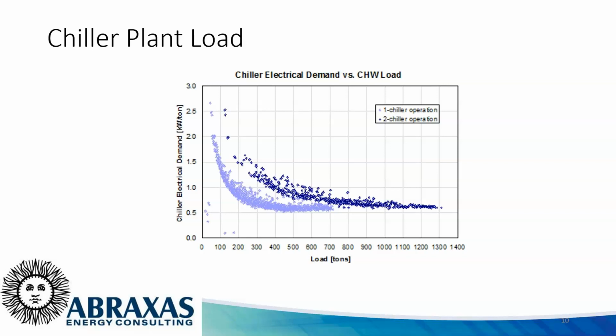They're still running two chillers when one chiller could satisfy the load. On the y-axis is shown the chiller electrical demand, and you can see how much higher the demand is running two chillers to satisfy the load. So clearly a waste of energy there, when they should be running just a single chiller a lot more than they were.